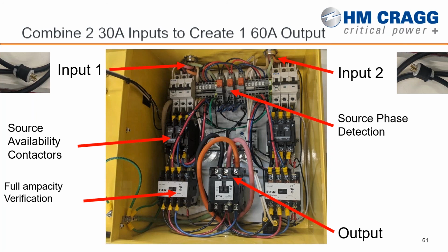Another issue they had on a previous design was that input 1 could be connected and powered up while input 2 was not. There was a safety consideration because if source 1 was installed and the second one wasn't, it would have live voltage on it before it was plugged into the second source. So that's where we implemented the source availability contactors to make sure it cannot travel upstream to the other cord.